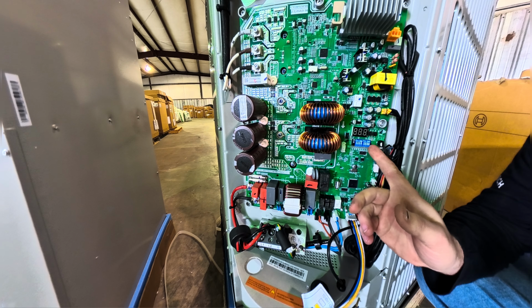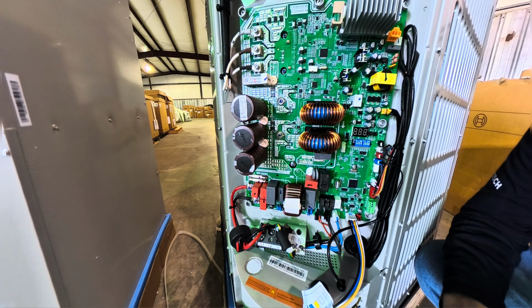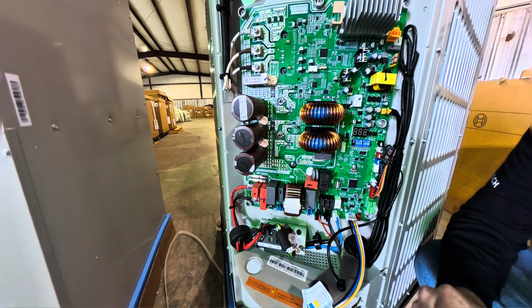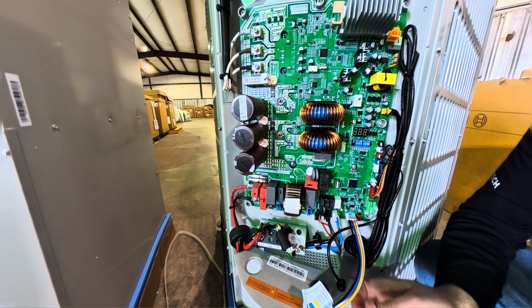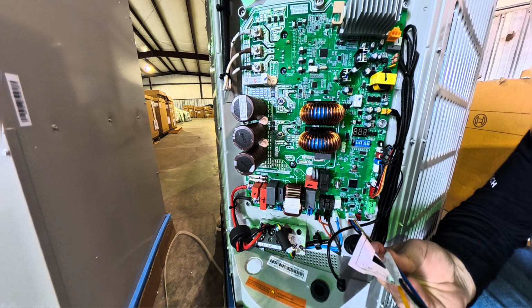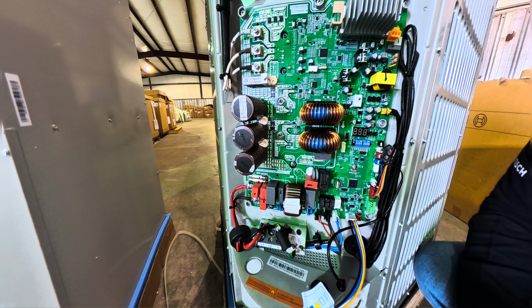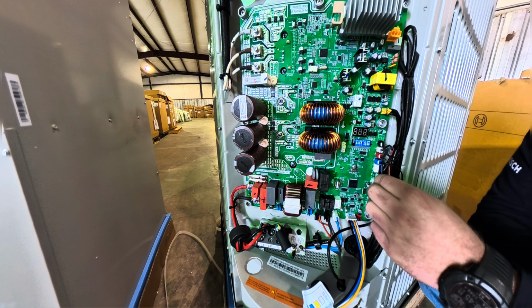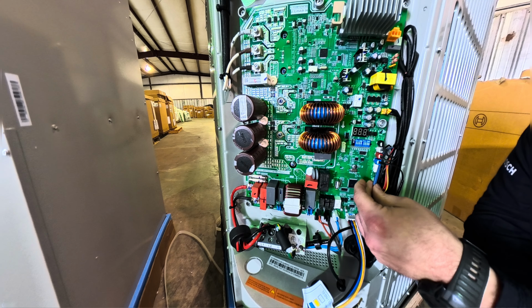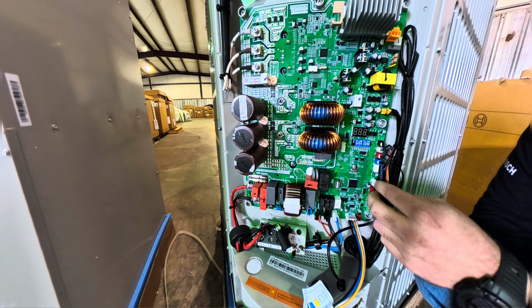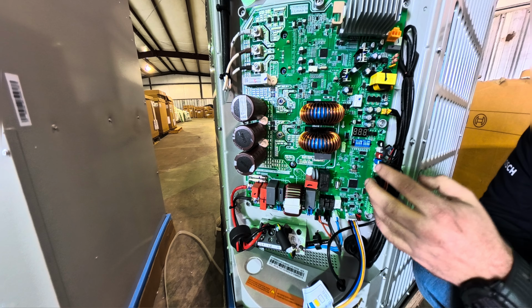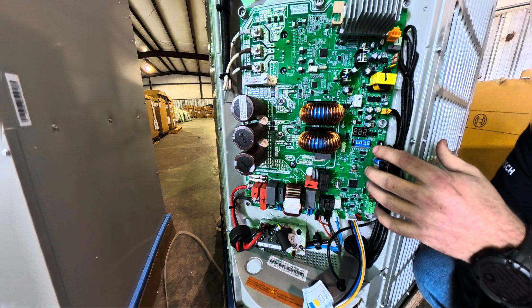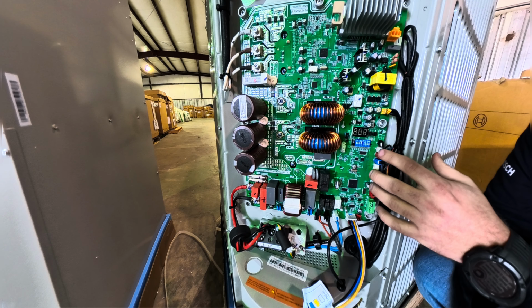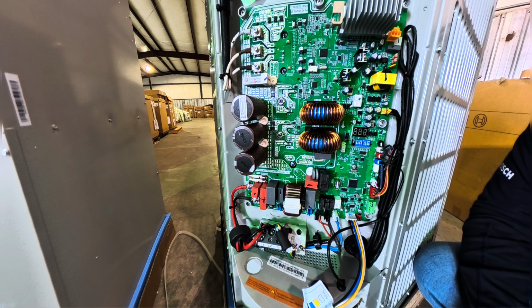There is a dip switch up here that you would use to switch it from communicating to non-communicating. Stepping on around, we have our EEV valve right here. These mini wires right here. Right here we have our pressure transducer, and then we have some temperature sensors. It's taking the data from these sensors and the pressure transducer to see what speed it needs to run.